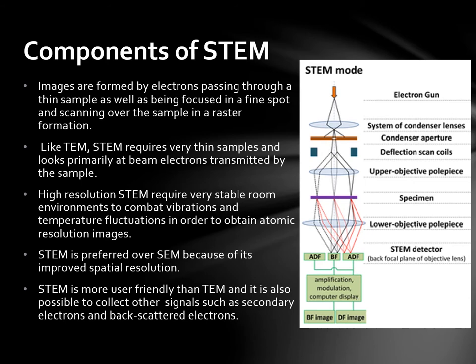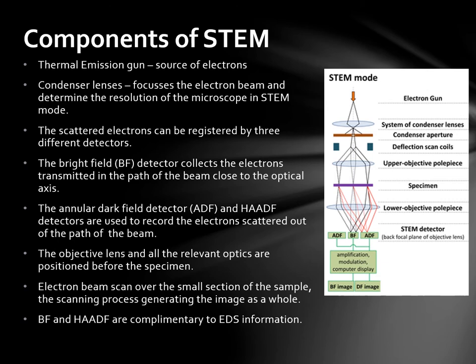Let's discuss some of the components of STEM. The thermal emission gun is the source of the electrons. Then we have the condenser lenses, which focus the electron beam and determine the resolution of the microscope in STEM mode. The scattered electrons can be registered by three different detectors. The Brightfield detector, abbreviated as the BF detector, collects the electrons transmitted in the path of the beam close to the optical axis. The annular darkfield and high-angle annular darkfield detectors are used to record the electrons scattered out of the path of the beam. The objective lens and all the relevant optics are positioned before the specimen, and the electron beam scans over the small section of the sample, generating the image as a whole.